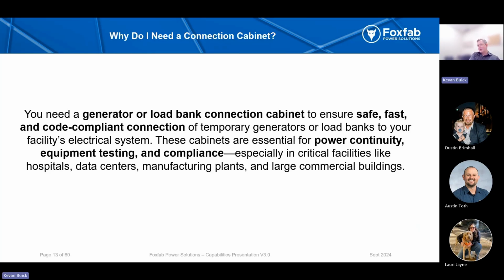So why do I need a connection cabinet? This question has primarily been answered, I think, in most of the jobs out there, but we still get end users coming to us that are new to the space and aren't totally sure why the connection cabinet might be a fit for them. You don't have to have a generator on site to need a connection cabinet. You can simply have a building where there is no generator available and you want the option to bring in a temporary generator, or you can have a building with multiple generators and want to pull them offline and service them while still bringing up a temporary generator.